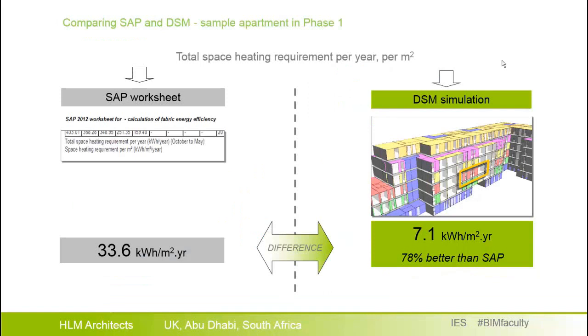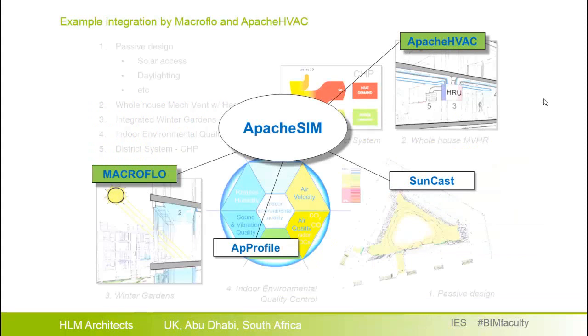We are using dynamic simulation to support, design, and assess the building. As you can see, there is a substantial difference between the SAP worksheet output and the dynamic simulation output — the DSM output is 78% better than the SAP in this direct comparison. There are several factors that contribute to this, and we are going to highlight two. We will see in detail two IES modules: Macroflo for the winter gardens, and Apache HVAC for the mechanical ventilation system.